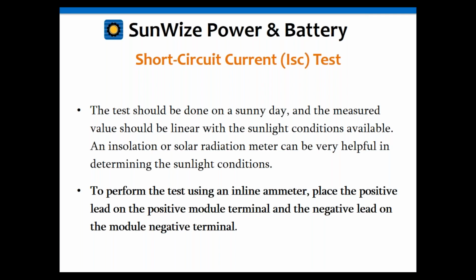And again, you would simply put the positive lead of the inline meter on the module positive terminal and the negative on the negative, and measure that current going through there. And when you're done, make certain you break that connection fast. Again, make certain you have your meter set to current, and make certain you have your leads adjusted for that.